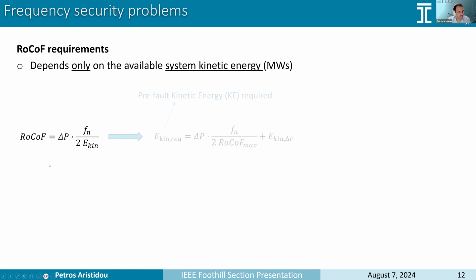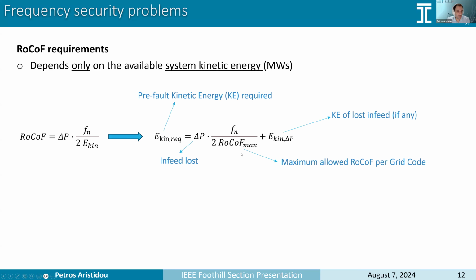If we take this function here and analyze it a little bit, we can compute the pre-fault kinetic energy that is required in our system to make sure that we keep the rate of change of frequency within the limit required by the grid code. Here we have delta P, the in-feed lost, so the generation lost. It could be, for example, from an HVDC link, or it could be the loss of a large generator. And also here we have this component, which is the kinetic energy provided by the in-feed lost.